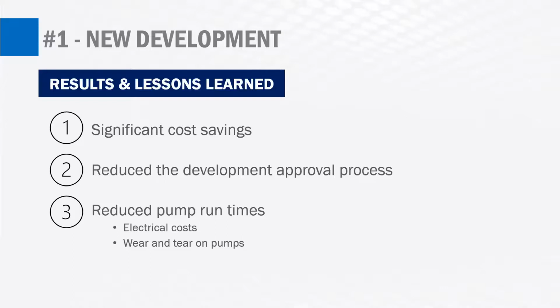So the development approval process was also streamlined as a result of this. The upgrades would no longer need to be designed and constructed. There was no cost sharing that would need to be worked out between the utility owner and the developer, so the approval process could run a lot smoother. Also, the performance of this station was greatly improved. The run times were drastically decreased, which would result in saved electrical costs and less wear and tear on the pumps and the other mechanical systems for this station.